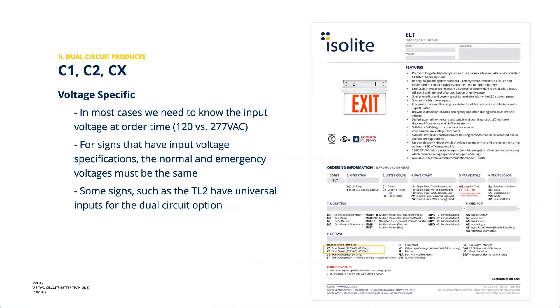In our cut sheets, C1 and C2 indicate voltage-specific versions — we need to know at order time whether it's a 120-volt or 277-volt system. Note that you cannot mix voltages: the normal supply and the emergency supply must both be the same voltage. However, some signs like the Thin Line have universal inputs for the dual circuit option, accepting both 120 and 277 volts, so you don't need to specify voltage at order time for those.